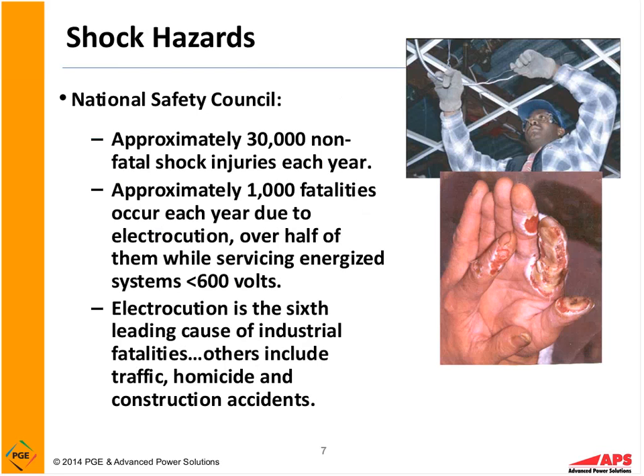Now, in the upper right-hand corner, you see a picture of someone working with the wires going to a lighting fixture. This is one of the areas we see a lot of injuries in, lighting fixtures, lighting ballast replacements, upgrades, etc., because sometimes people don't understand the level of shock that can occur with those and don't necessarily take the same level of precautions. The picture just below it shows someone that actually has had an electrical contact burn. This is not from an arc flash, but from electrical current flowing through their body because they got stuck on electricity. As the current flowed through their body, it actually caused part of their skin and the tissue underneath it, excuse the expression, to actually cook. So this contact burn caused severe injury to this person.